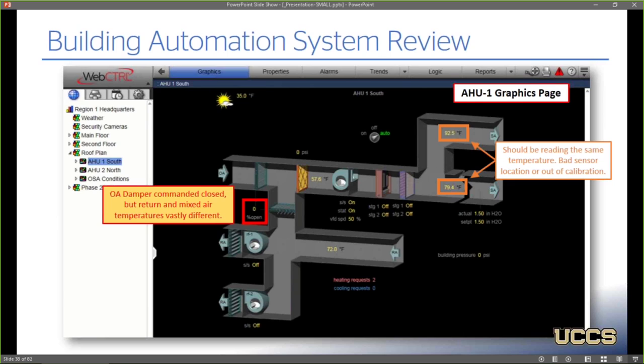The outside air damper here is commanded shut, but if you look at the return air and the mixed air conditions, we have a return air of 72 and a mixed air of 58. So that suggests that the outside air is actually open quite a bit. And if you change that setting, if you override it, you don't see any change in the mixed air temperature sensor, which suggests the outside air dampers probably failed in some fashion.